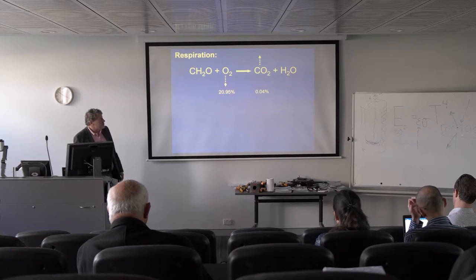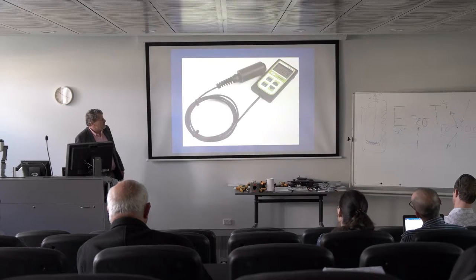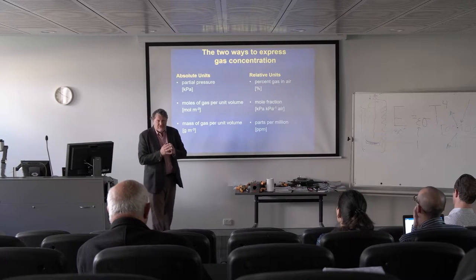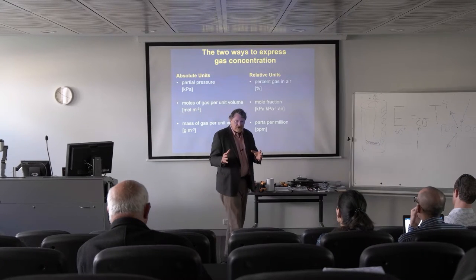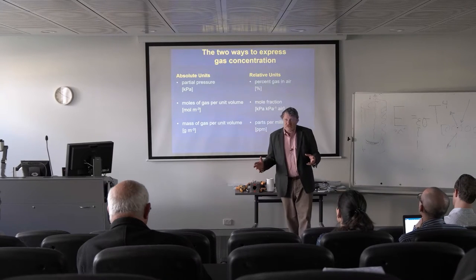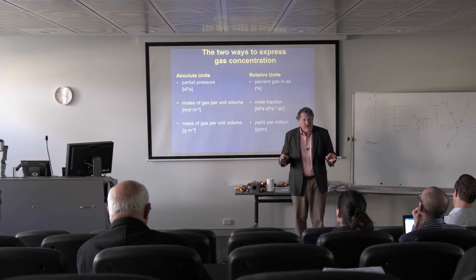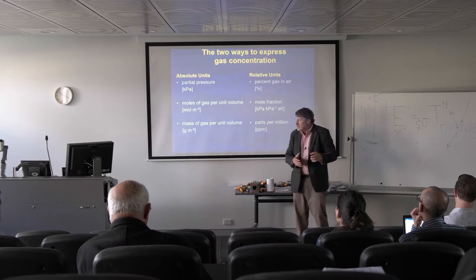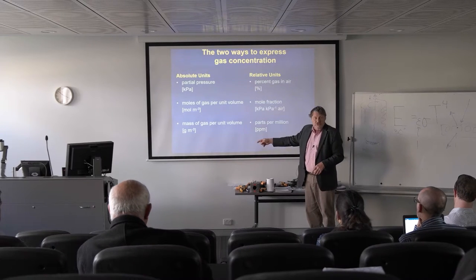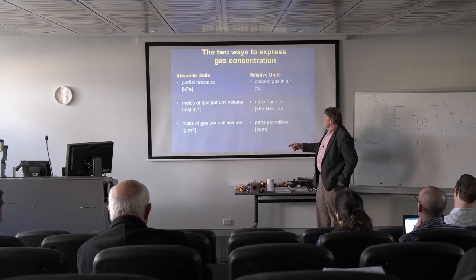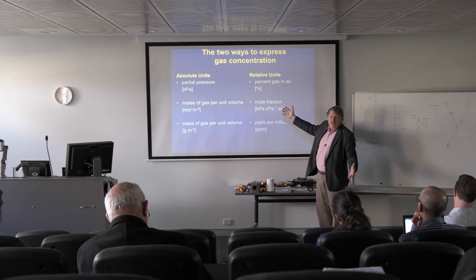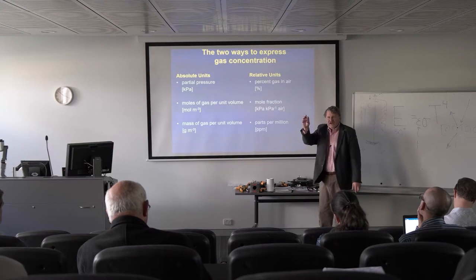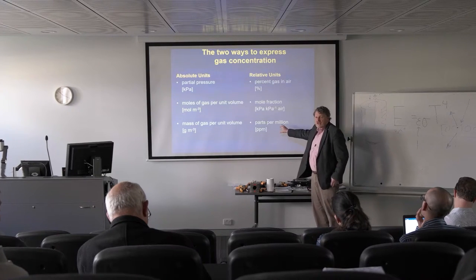Of course the background of oxygen is much higher. Here's a picture of the sensor with the meter and the sensor on the end. To come full circle — in the very first talk I talked about relative and absolute humidity, the water vapor in air. That same principle applies to all gases in air. We have relative measurements and absolute units. Relative, not surprisingly, is percent — the same exact concept as relative humidity. We can call that mole fraction: the pressure of oxygen divided by total pressure, or parts per million — another measure of the same thing.